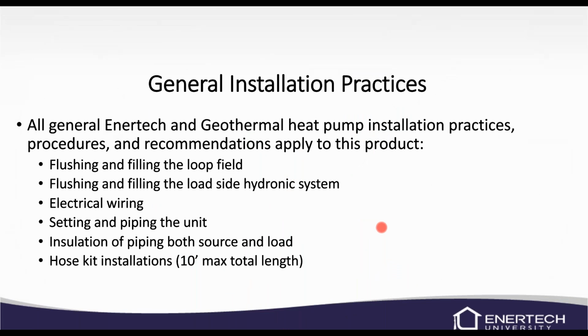So all general Enertech and geothermal heat pump installation practices, procedures, and recommendations all apply to this unit. What I mean by that is you still have to flush and fill the loop field. You still have to flush and fill the load side hydronic system. There's still the same type of electrical wiring, breakers from the panel. You're still going to have to set and pipe the unit and insulate both the source and load piping.